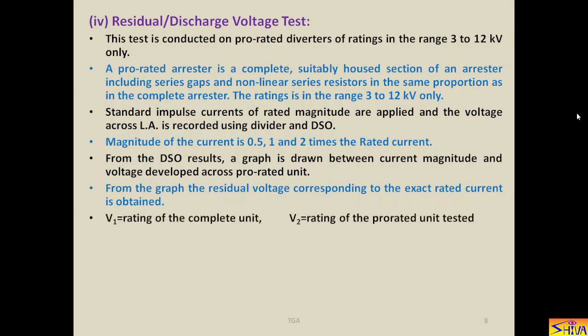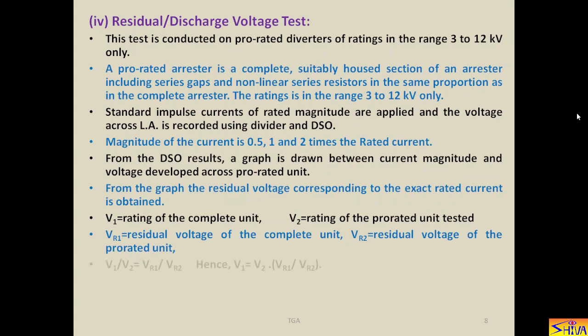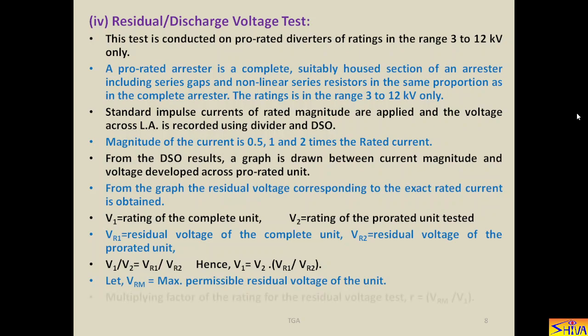Let us say V1 is the rating of the complete unit, V2 is the rating of the prorated unit tested, VR1 is the residual voltage of the complete unit, VR2 is the residual voltage of the prorated unit. Then V1 upon V2 will be equal to VR1 upon VR2, that is direct proportion. Hence V1, that is the rating of the complete unit, will be equal to V2 into VR1 upon VR2. Let us say VRM is the maximum permissible residual voltage of the unit.